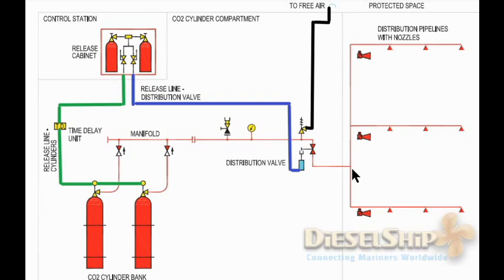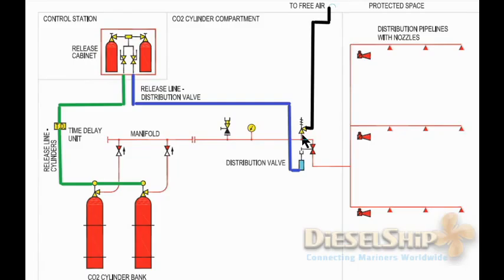Now let's concentrate on the main manifold. You definitely need a blank here so that for any maintenance purpose you can isolate the CO2 bottle section, blank it off, and carry out maintenance. There is also a valve through which you can connect air from either the engine room or from shore depending on whether you are in dry dock. On the manifold there is a pressure gauge indicating whether the line is pressurized, and one of the main components is the relief valve. If CO2 is released but the distribution valve has not opened, the relief valve will lift and the CO2 will vent to free atmosphere outside the CO2 room.